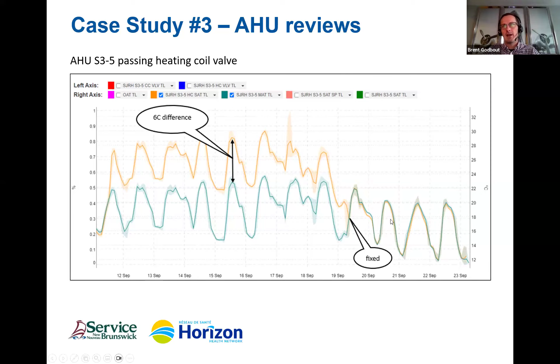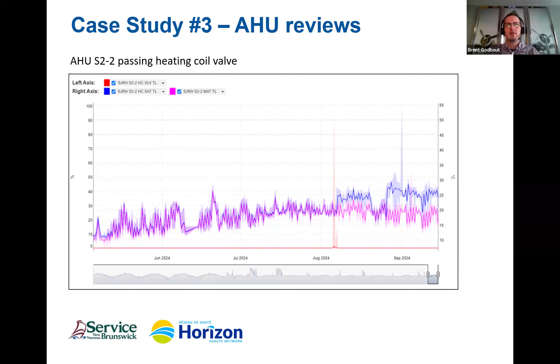This was the other one, displayed a little differently. This one goes back to the start of the summer. You can see here the temperature before and after the heating coil was about the same, so we weren't leaking at that point, but then boom, started leaking. Then it went away, and then it came back. This one, the first one, we just had to stroke the valve 3 or 4 times, and then it was seating itself properly. So that took care of that one. But this one, we actually had to change the valve itself, it was just malfunctioning at times. So the heating coil valve had to be changed out.